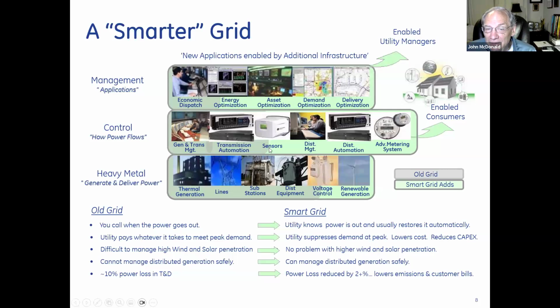In the middle, sensors: we've been adding instrumentation and sensors to the grid, but we have new specialized sensors today. For instance, I draw oil from the transformer and pass it through a sensor, and I can detect gases dissolved in that oil. Each gas I detect corresponds to a failure mode occurring in the transformer. I can detect up to 9 different gases dissolved in the oil of the main tank. This is important because it shows a failure is occurring, and we want to prevent a catastrophic failure.